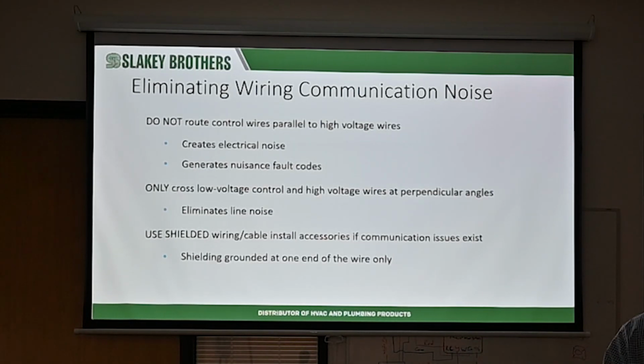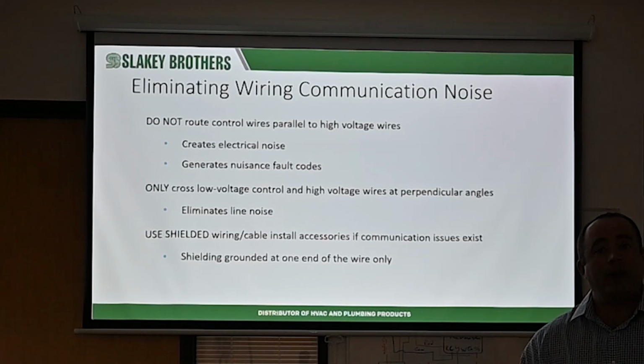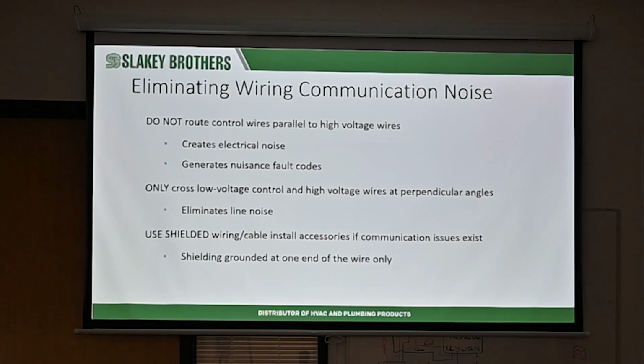This is where we're going to go over how to get into the Connex a little later, to look for past faults, to see why it wasn't working. Because sometimes a customer doesn't really see, hey, I got a communication fault. They just say, I was turning it up and down and nothing would happen. They just won't do anything. It's because they didn't notice that it had a fault for communication.